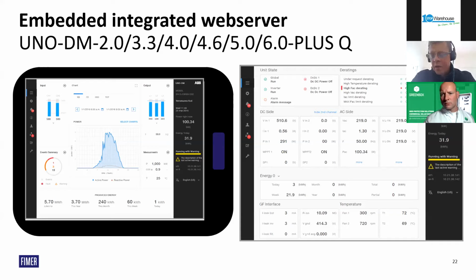So if the customer mentions that the inverter is not performing as well as it should do and there's no alarms, you can easily go in here and see if there are any derating factors like temperature or high grid voltage. Also, there's a menu on the left for alarms, so you can download any alarm event lists. You have access to all the parameters for group support functions, network functions, so you can change the customer's password, or if they upgrade to the NBN, you have easy access to do that sort of work as well. So a very handy, powerful tool.